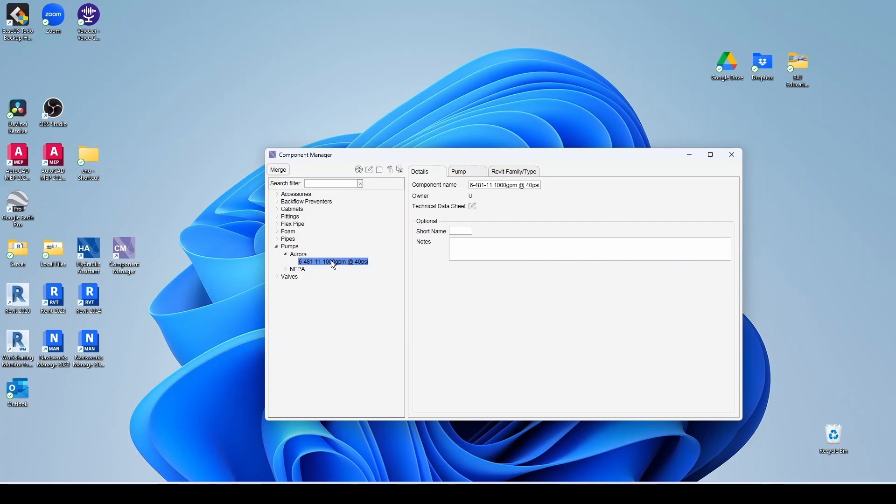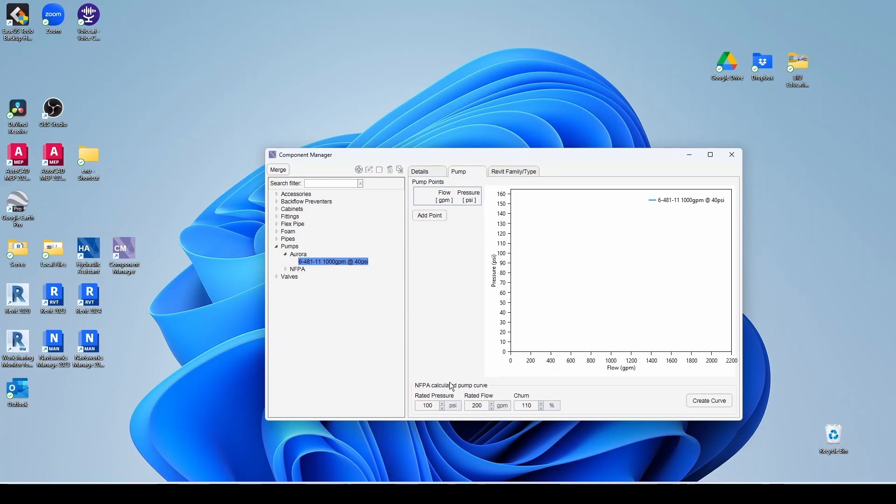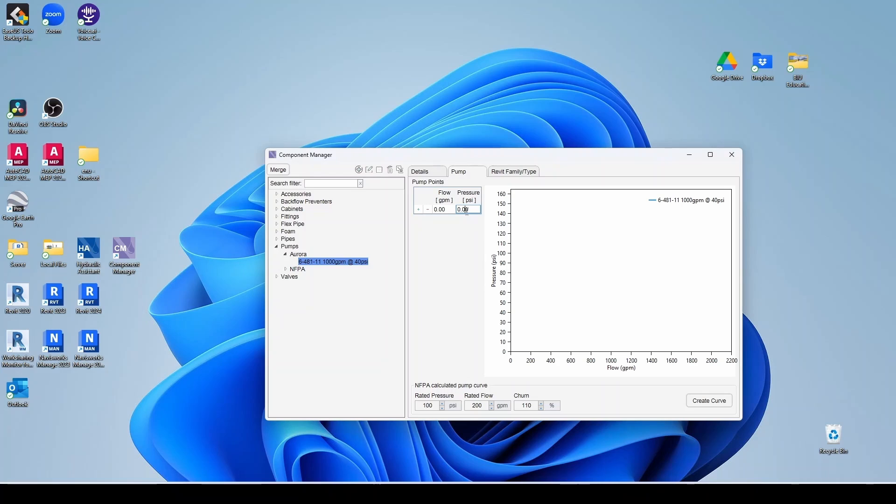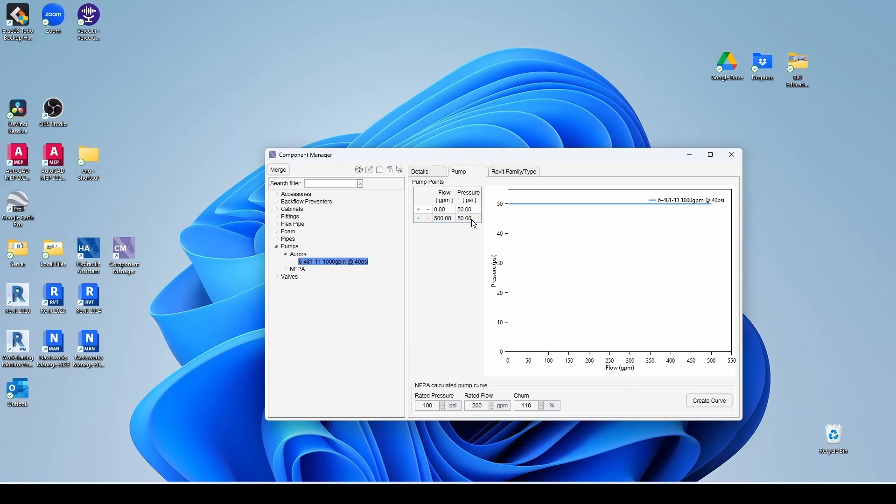Now, in this case, instead of being an NFPA calculating pump curve, I'm going to introduce real points based on the performance curve that I got from the manufacturer. So at point, you always want to have your churn. In this case, it's going to be 50. Then maybe we can have like 500 GPM, half of the rated flow. And let's say that's 48 PSI.